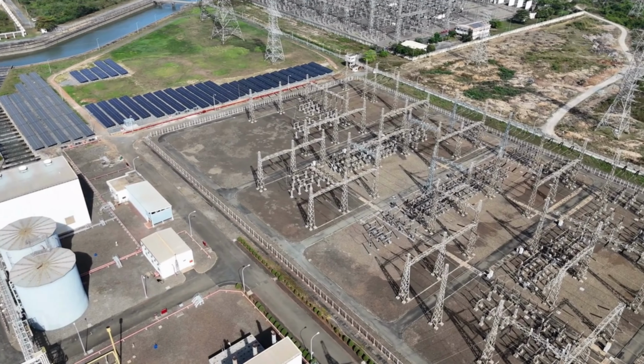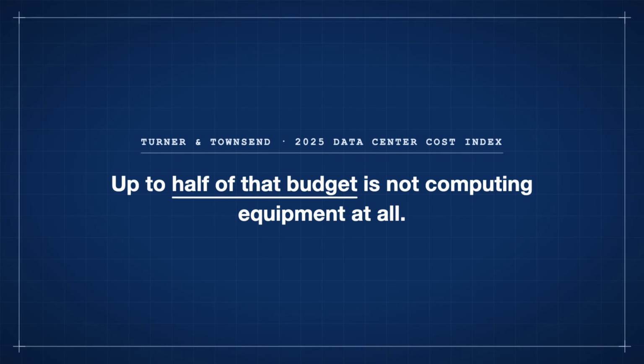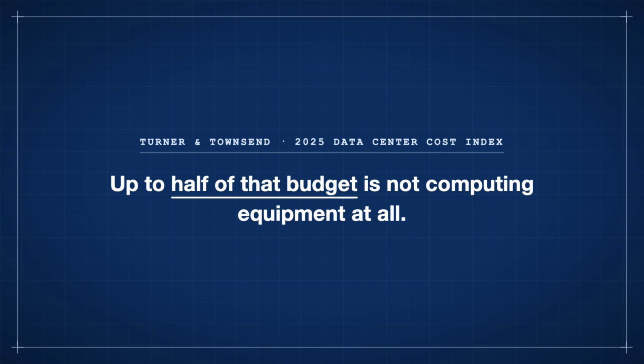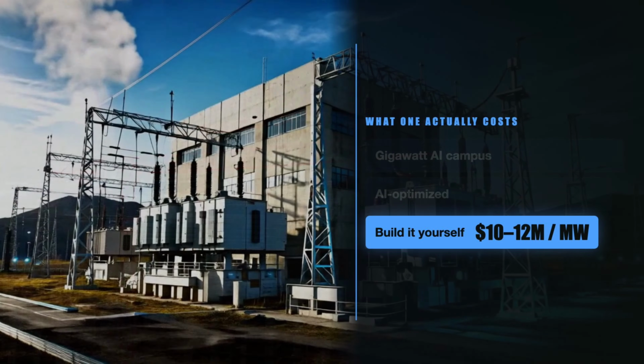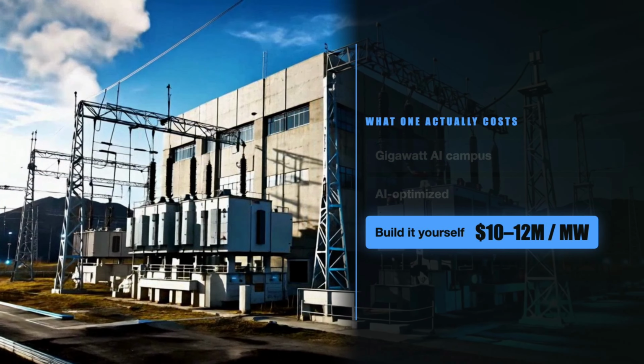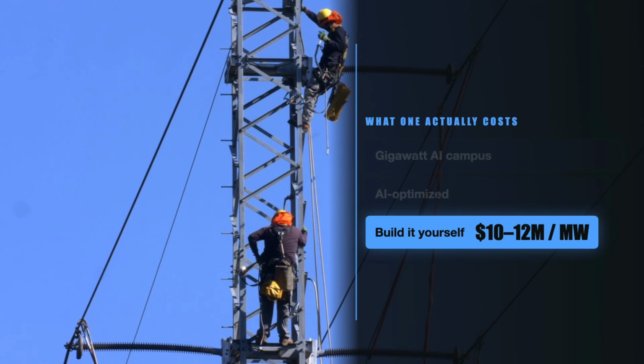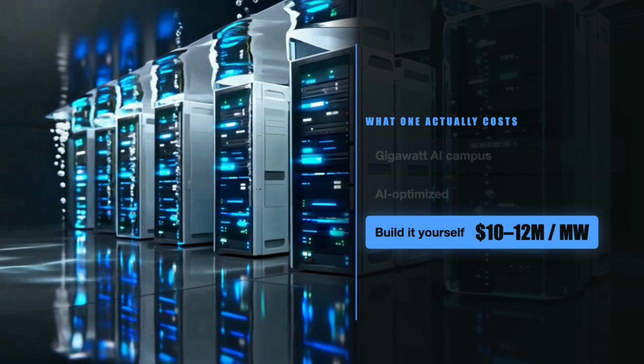The next rung up, you build a real facility. The rule of thumb the industry uses is about $10 to $12 million per megawatt of capacity for a standard build. And here is the first uncomfortable detail: up to half of that budget is not computing equipment at all. It is the mechanical and electrical guts, the transformers, the switchgear, the backup generators, the cooling. You are not building a computer room. You are building a small power plant that happens to have servers bolted onto the end of it.